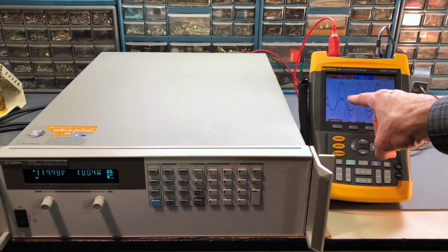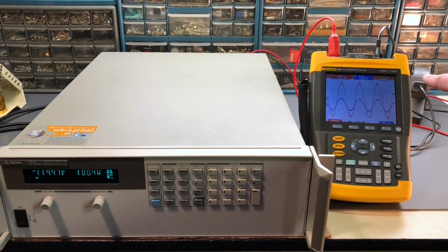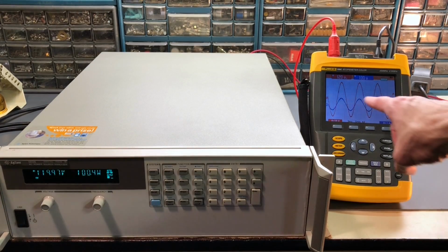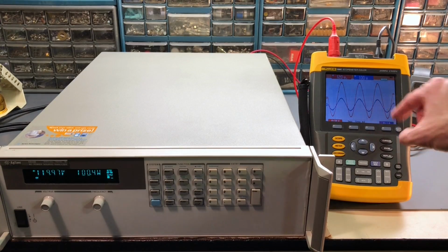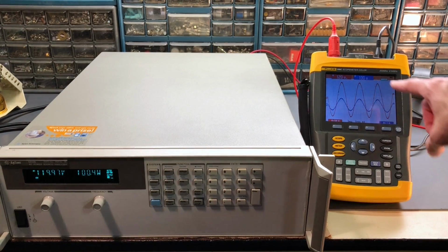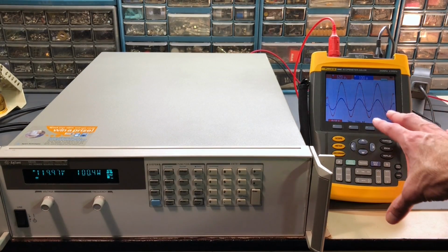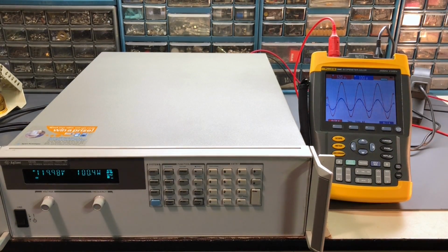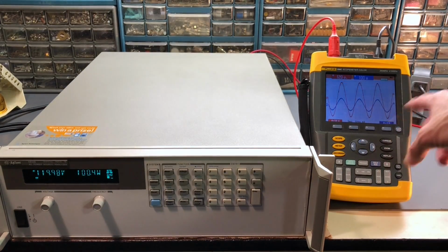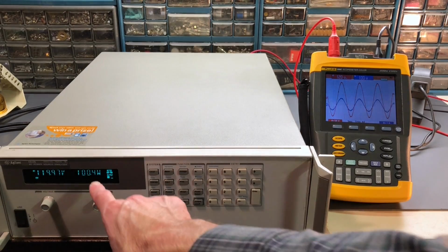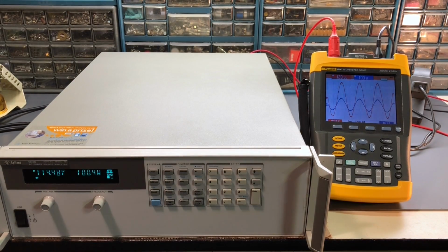And then the blue trace over here is the current waveform. So if you look over there, that's a current clamp that's sitting back there, and you can see that little red wire that's passing through it right above my finger back there. So that clamp is just around that red wire, and it's measuring the current going over to the incandescent bulb. So we can see that the current is in phase with the voltage, which makes sense on a resistive load. So no issues there. And then this is indicating 100 watts. So I have this Scopemeter calculating the wattage, and it can do that because it knows what the voltage is and it knows the current, so it just makes a wattage calculation. And over here we can see this is also indicating 100 watts. So everything matches up, looks spot on, no issues whatsoever.